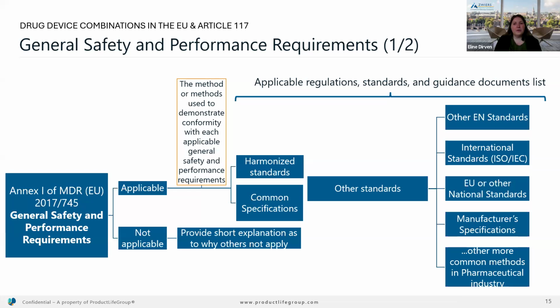We have usually been successful for the sterilization method, in that we can just apply the method of the pharmaceutical industry instead of switching to the harmonized standard for sterilization in the medical device industry. We have also been successful, if it's just a relatively easy scale bar, in using the common pharmaceutical method to demonstrate the accuracy of that scale bar. So it's good to realize that maybe you don't need to switch everything towards other, unfamiliar standards.